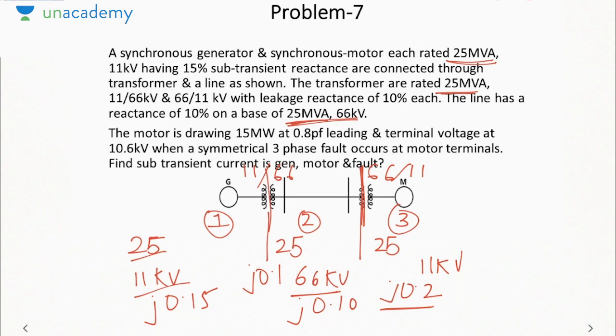The terminal voltage is 10.6. So let me calculate the pu values. 15 by 25 is equal to 0.6 pu. And the terminal voltage is 10.6, which will be divided by 11 because it is talking about section number 3. So it will come out to be 0.9636.